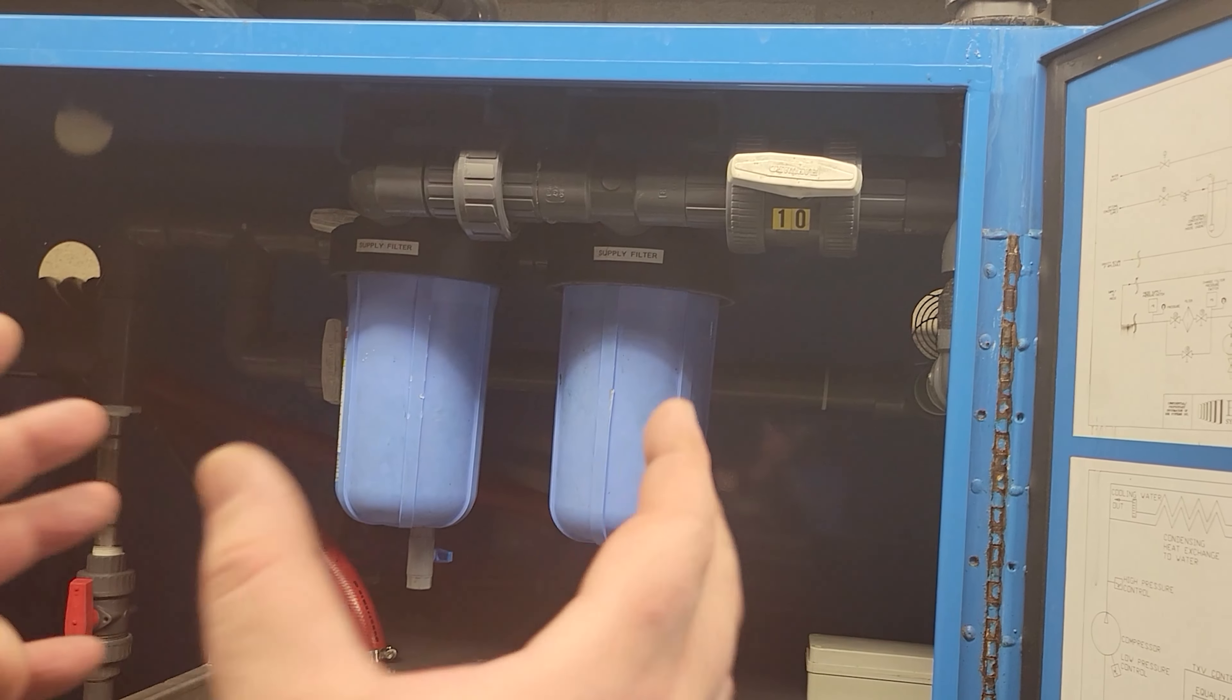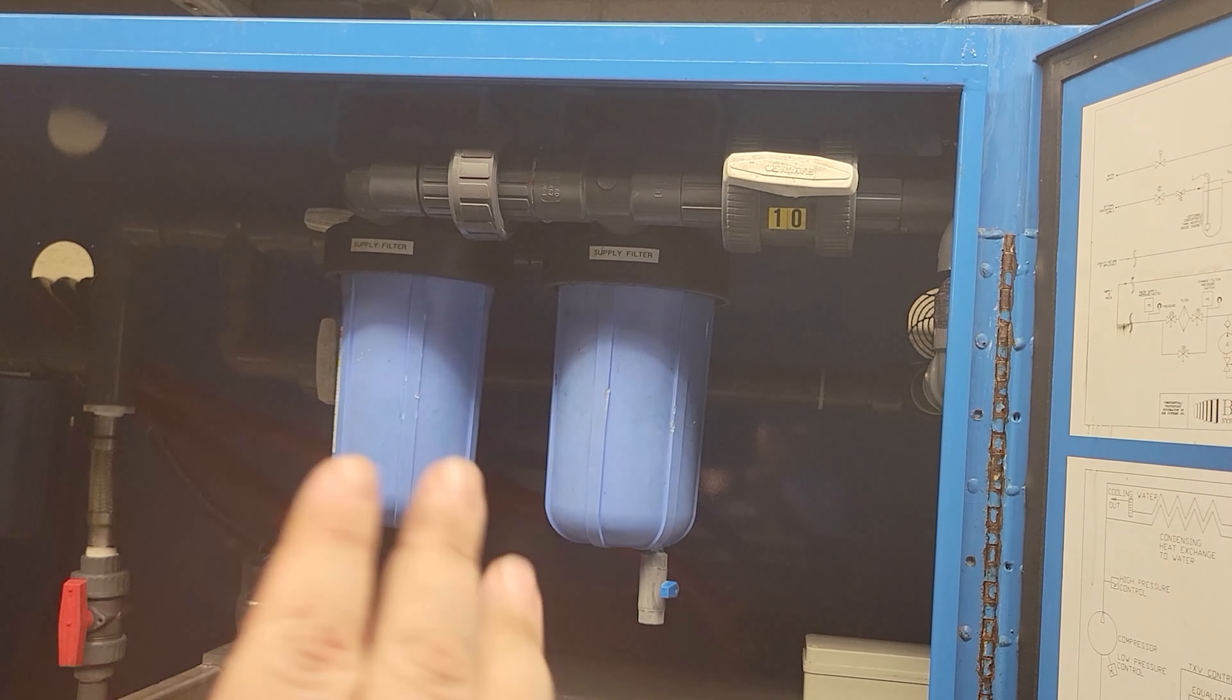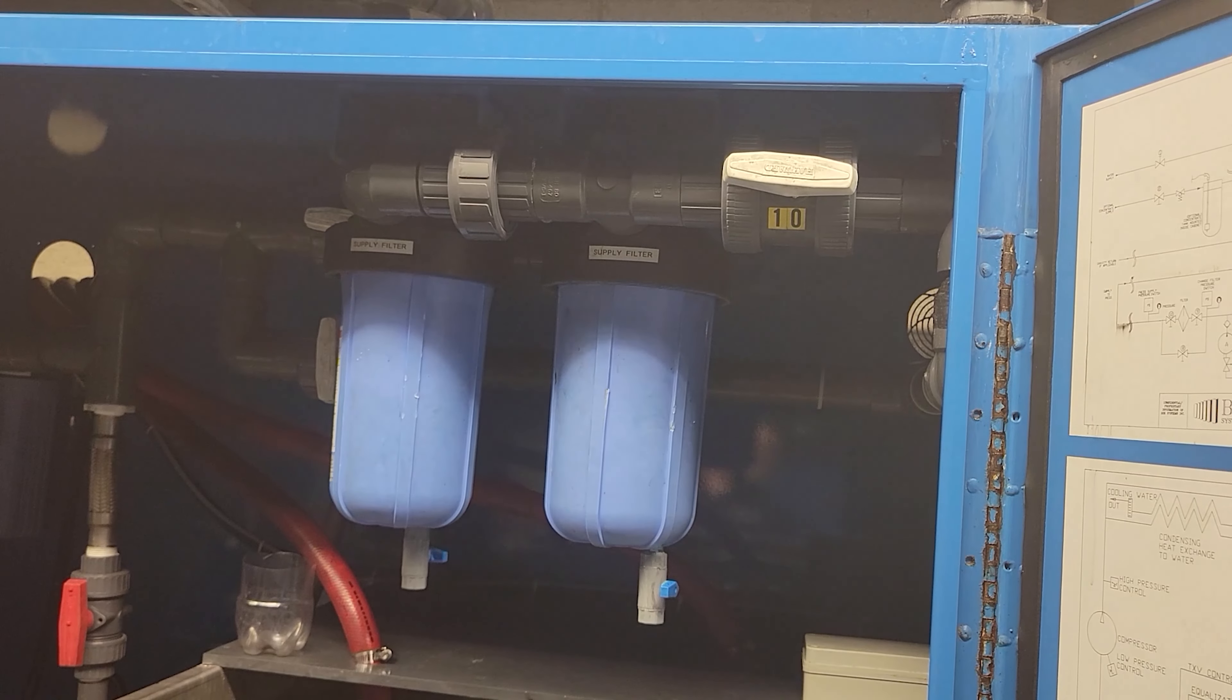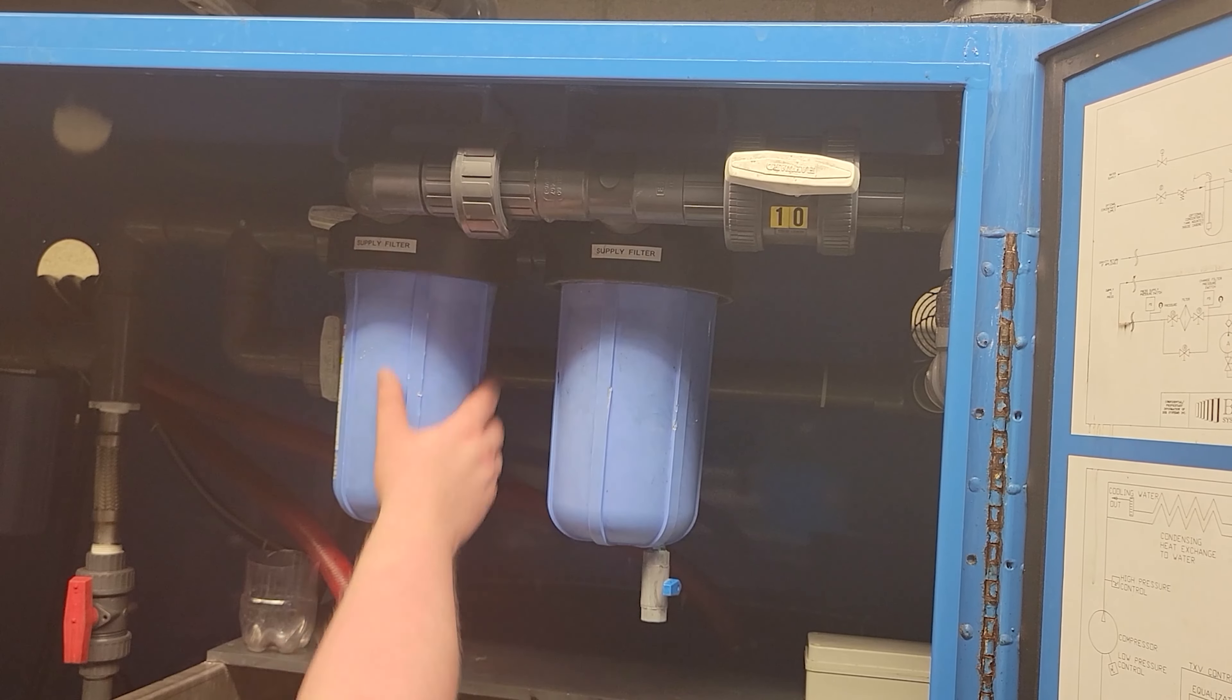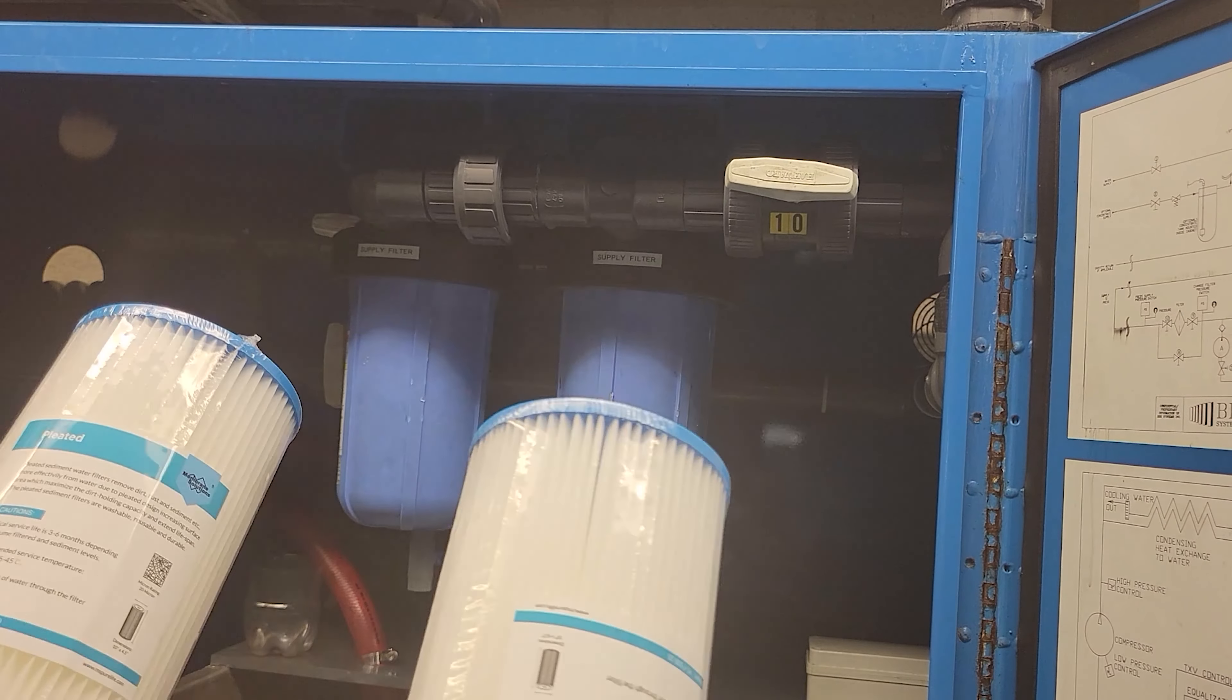As long as you don't really crush those things down, there's an o-ring on the top. If you flatten that out too far, it'll develop leaks. As long as you don't do that, just do those light taps, you shouldn't have any problem with that. So that's two, and I got two left. Nice, easy job.